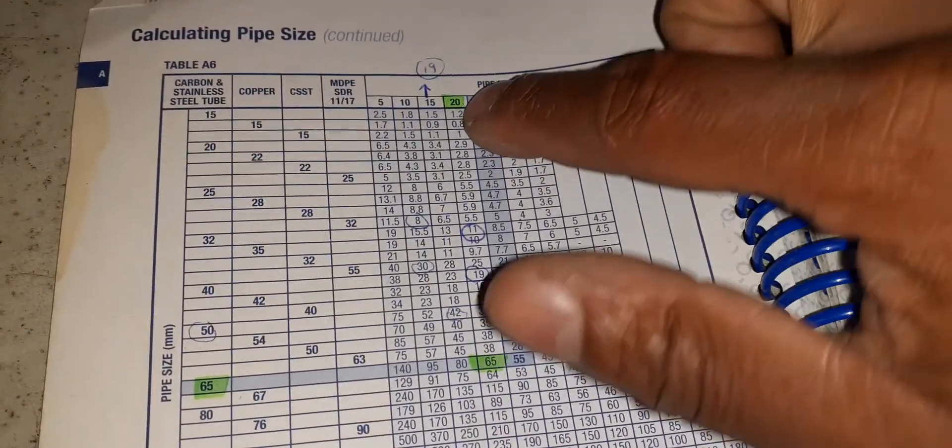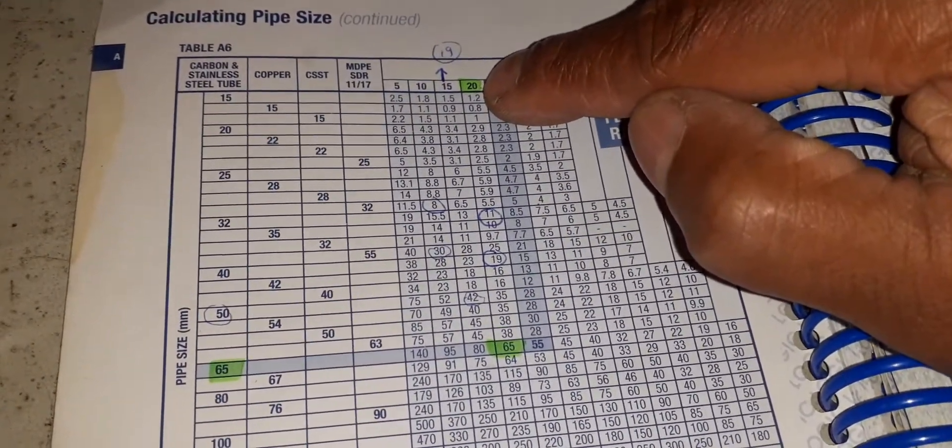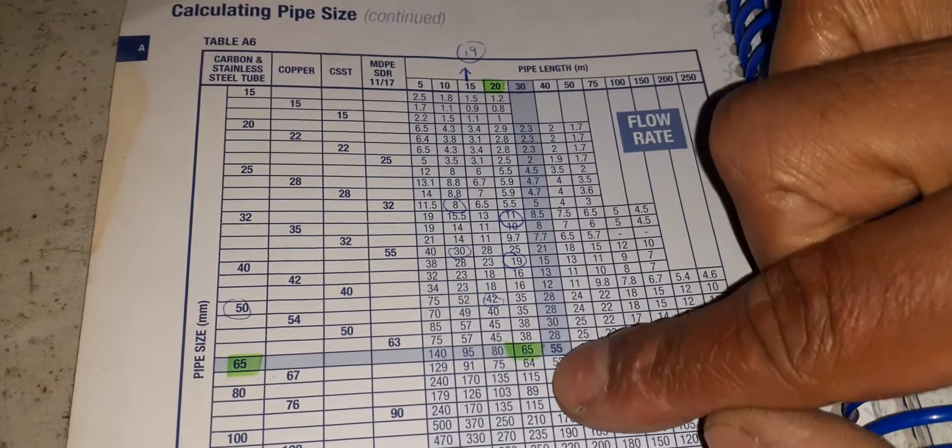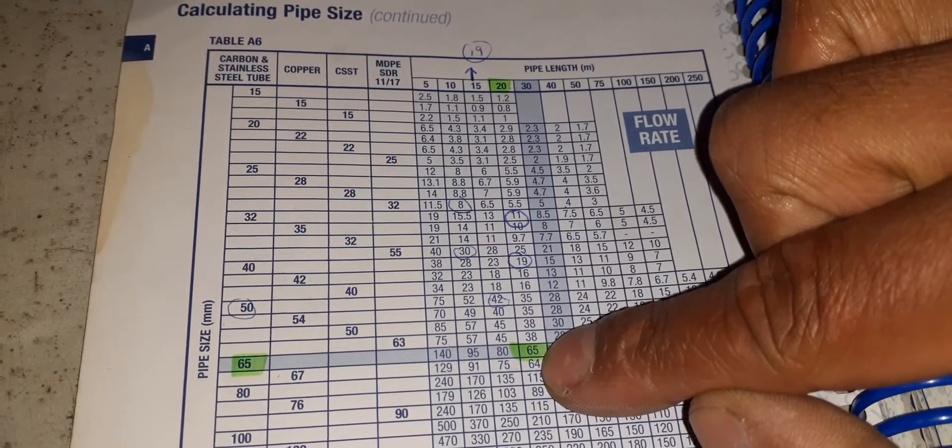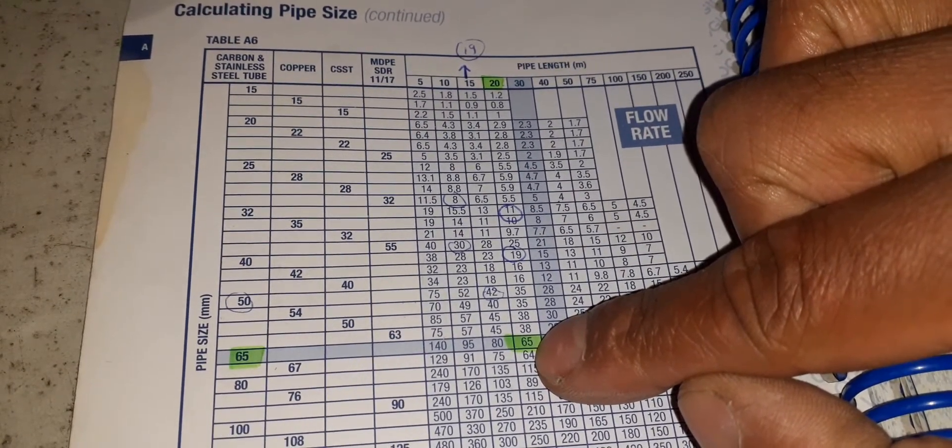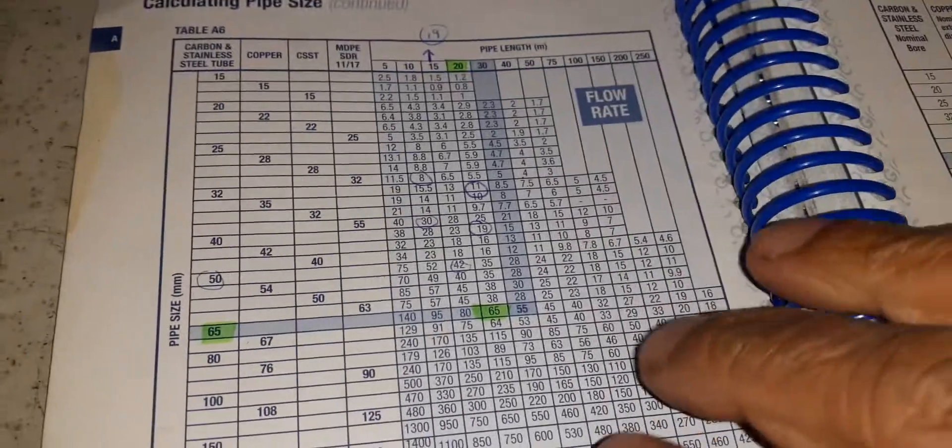65 mil will get us to 20 meters straight line of gas and give us this flow rate here, 65 meters cubed an hour. That will deal with our 18 meters.